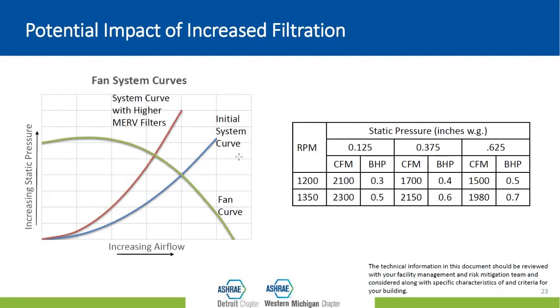A couple of other things that you want to be aware of with increasing the MERV value of your filters. You want to make sure that the new filters can fit into your equipment, right? If your existing equipment has a 1-inch rack and it accommodates a 1-inch filter, you want to make sure that if you increase your MERV value, your new filters are also just 1-inch. Or then you make a decision to modify your equipment to accept either a 2-inch filter or a 4-inch filter or some other depth of filter.